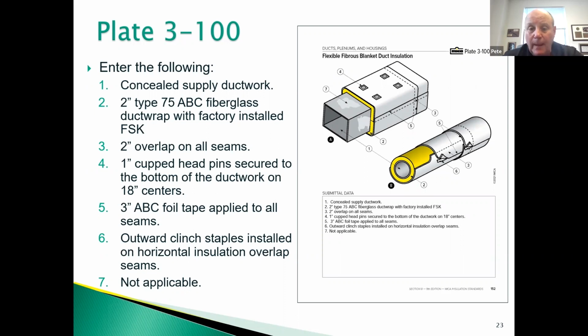Number 7 shows adhesive on the ductwork. In this example, we're going to say not applicable, because on this project we're not using adhesive on the ductwork before installing the insulation. But if you're doing an Army Corps of Engineers project, they might require it. So you would list number 7 and state the type of adhesive you're putting on the ductwork and where you're putting it on—it might just be on the sides and bottom, all 4 sides, or just the bottom. You would list exactly where you're installing the adhesive. But again, in this example, we're not using adhesive, so we'll say not applicable.